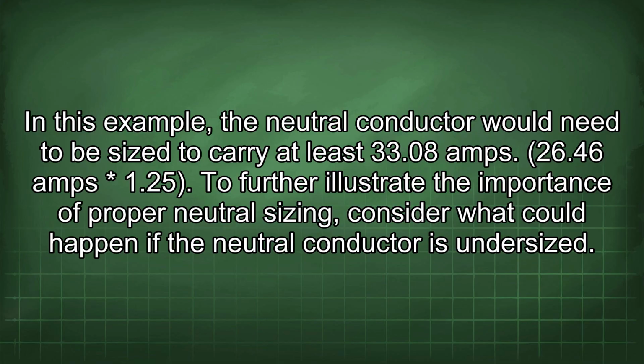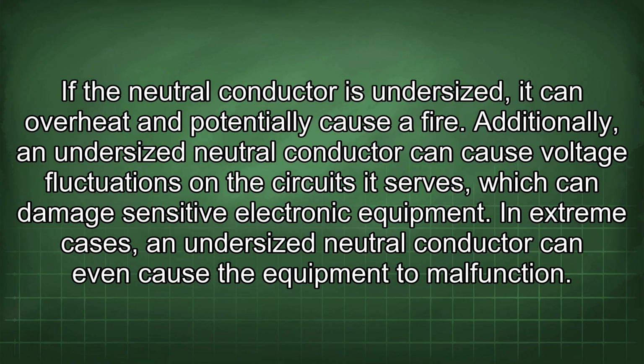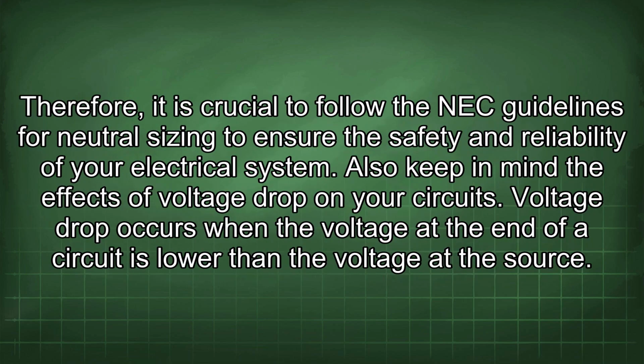To further illustrate the importance of proper neutral sizing, consider what could happen if the neutral conductor is undersized. If the neutral conductor is undersized, it can overheat and potentially cause a fire. Additionally, an undersized neutral conductor can cause voltage fluctuations on the circuits it serves, which can damage sensitive electronic equipment. In extreme cases, an undersized neutral conductor can even cause the equipment to malfunction. Therefore, it is crucial to follow the NEC guidelines for neutral sizing to ensure the safety and reliability of your electrical system. Also keep in mind the effects of voltage drop on your circuits.